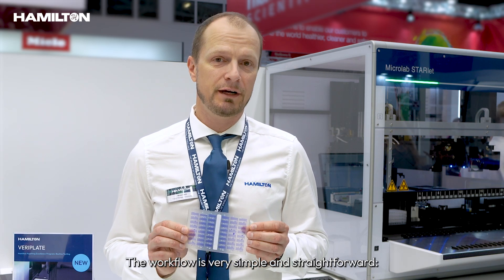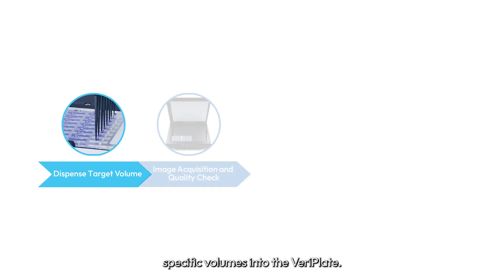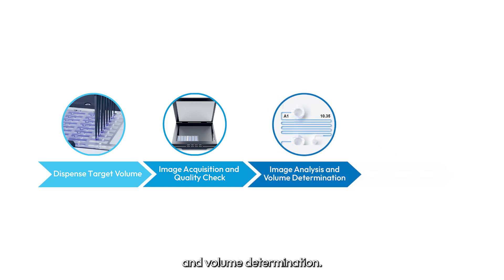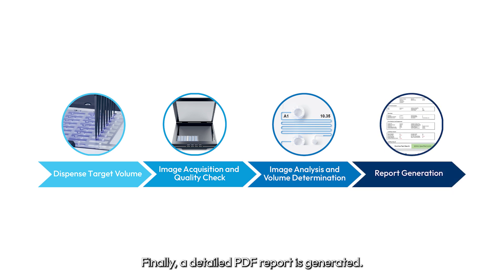The workflow is very simple and straightforward. First, the automated liquid handling system pipettes specific volumes into the VeriPlate. Then, an optical scanner images the VeriPlate, allowing for an automated image analysis and volume determination. Finally, a detailed PDF report is generated.